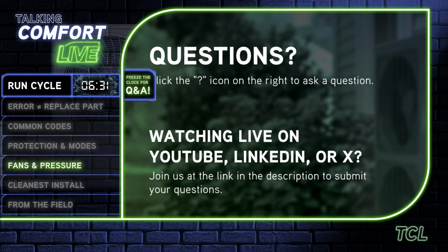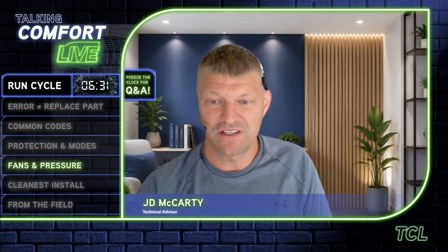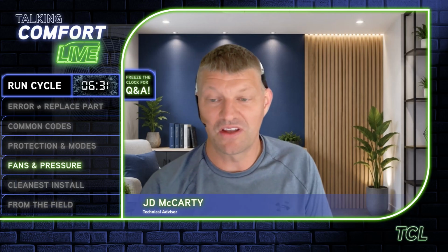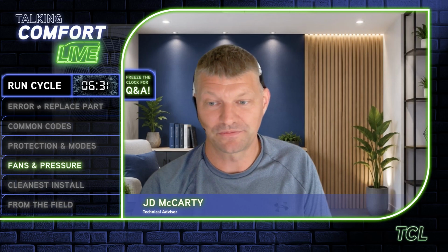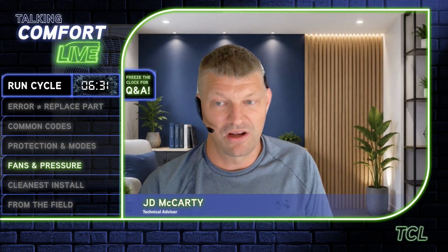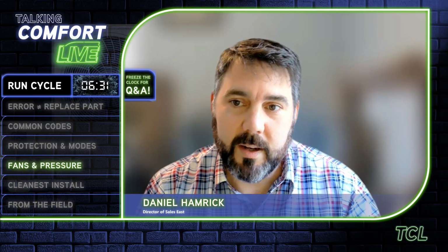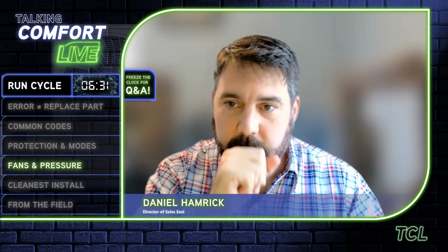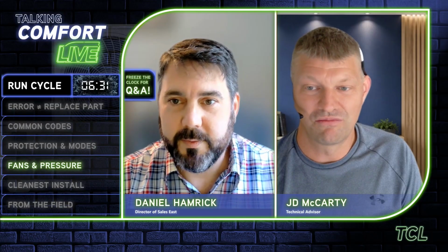The primary unit, I believe a 12K, almost never seems to blow cold according to the owner, unless the other 2 units are turned down or off. They're constantly freezing over like blocks of ice. Okay. This must be a multi-outdoor with indoor units.